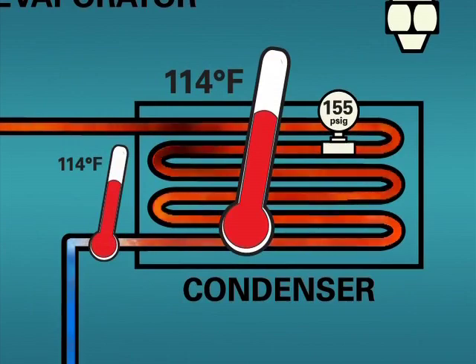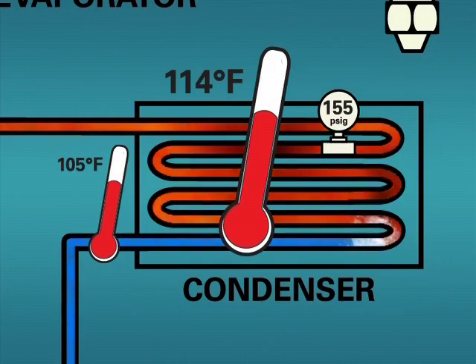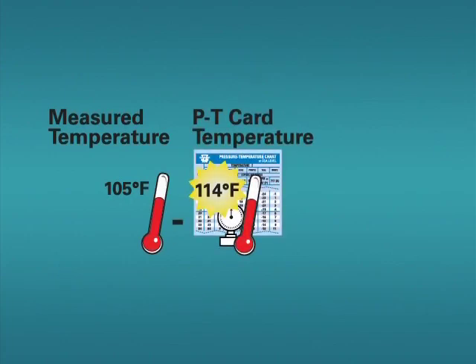If 114 degrees Fahrenheit is measured at the condenser coil outlet, we know the refrigerant is still saturated, and we likely have a liquid and vapor refrigerant mixture entering the liquid line. However, our actual measured temperature in this case is 105 degrees Fahrenheit. Because this temperature is lower than our saturated temperature, we know the refrigerant at this point is subcooled liquid. To determine the amount of subcooling, simply take the difference between the measured temperature and the saturated temperature indicated by the PT card. In this case, the difference between 114 degrees Fahrenheit and 105 degrees Fahrenheit is 9 degrees Fahrenheit subcooling.